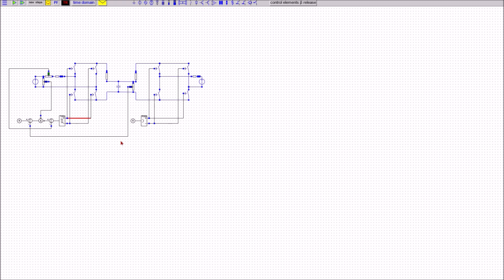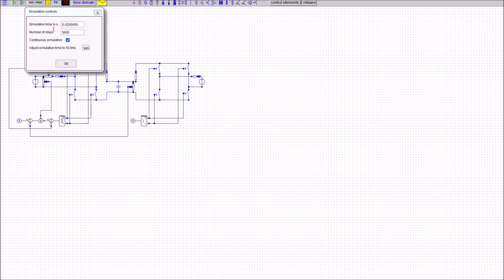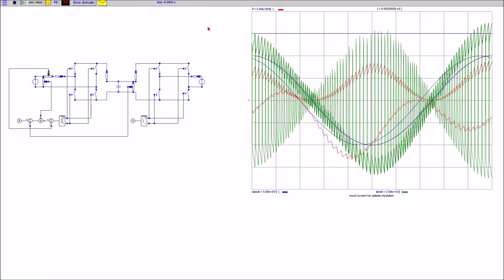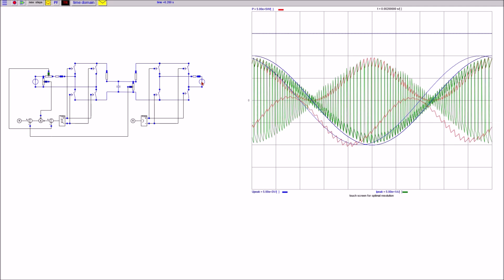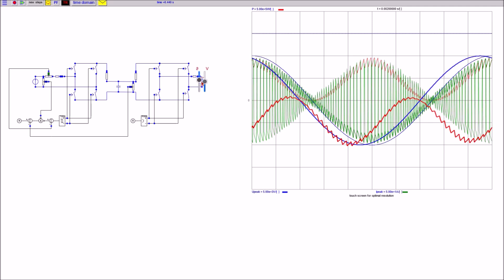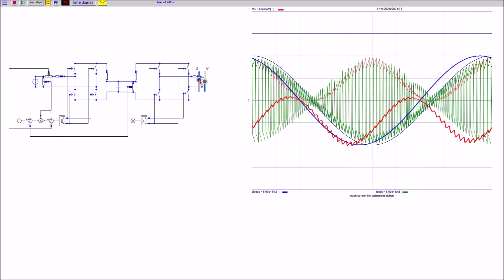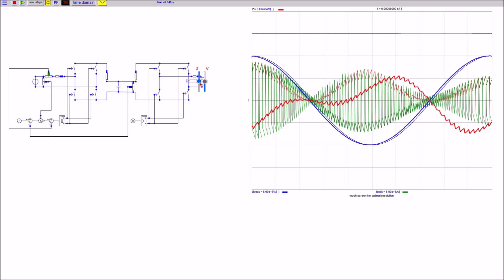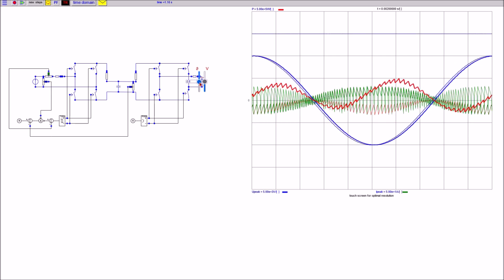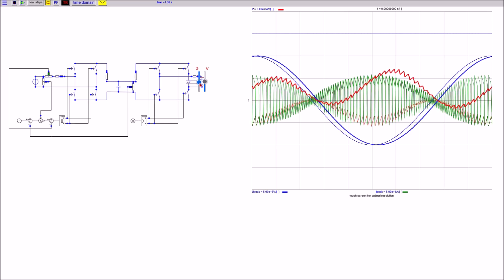Bringing it all together: a voltage source HVDC connection consists of two converters at each end of the line. The converter on the right side is controlled by a very simple pulse width controller with a fixed frequency and fixed angle setting. This converter controls the power flow on the right side automatically by means of the phase angle difference between the AC source on the right side and the AC side of the right converter.